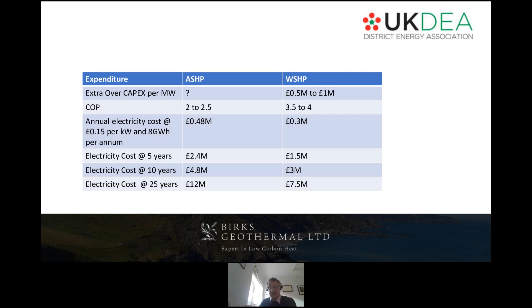Looking at this here, within 5 years, one would expect the extra over capital cost of the well field to be compensated, and thereafter the cost savings become fairly considerable. And looking at organisations such as PFIs and local authorities who are looking at whole life periods, beyond the 5-year payback period, you start to see that water source heat pump technology comes into its own. But, and it's a big but, for the business case to work, these higher coefficients of performance have to be sustained.